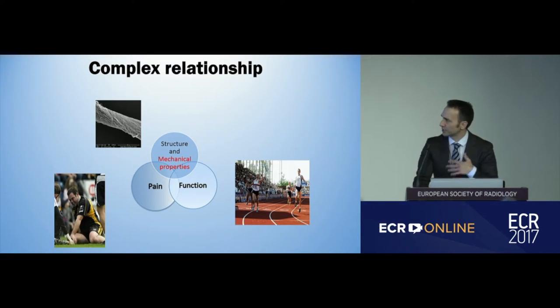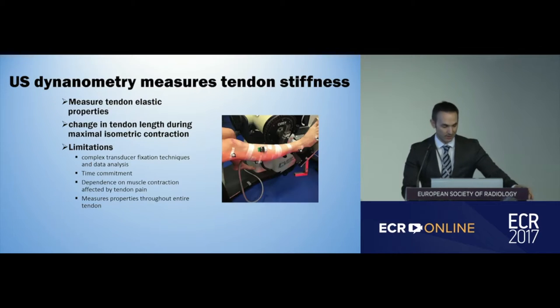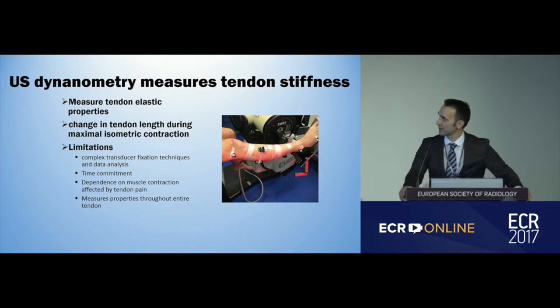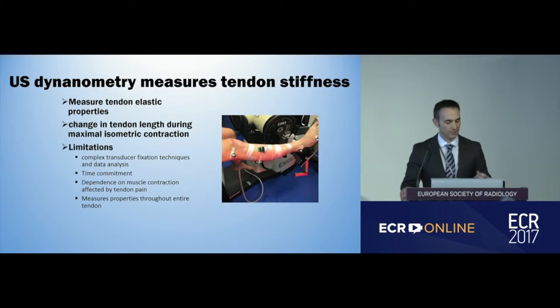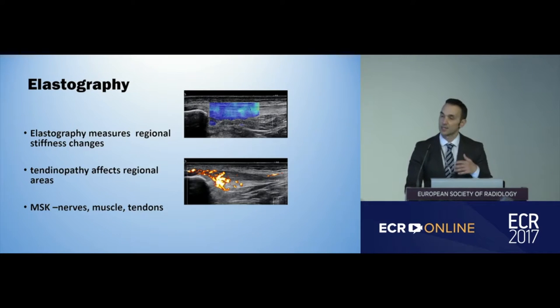We have this complex relationship between structure, mechanical properties, function, and pain. Shear wave elastography is able to actually measure the mechanical properties of the tendon and might improve our outcomes. Traditionally, tendon stiffness was measured using ultrasound dynamometry, which measures tendon elastic properties by looking at change in tendon length during maximal isometric contraction. But this technique has many limitations — it's very complex, with transducer fixation issues, data analysis, and time commitments, and it's dependent on muscle contraction, which is affected by pain. It also measures properties throughout the entire tendon, whereas tendinopathy involves regional pathological changes.